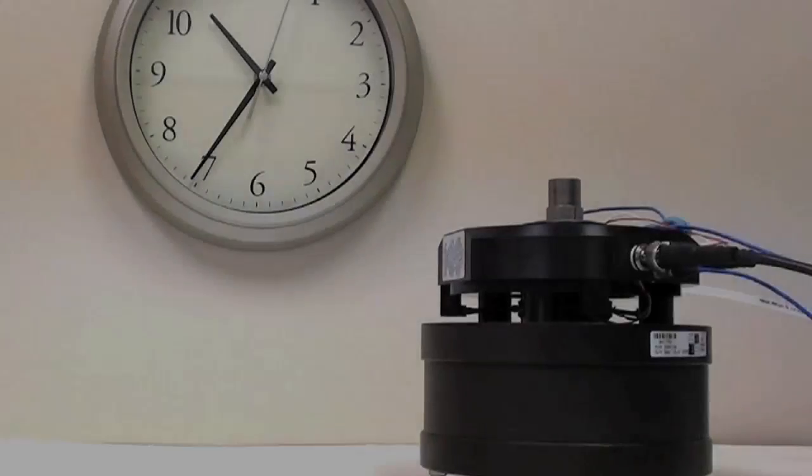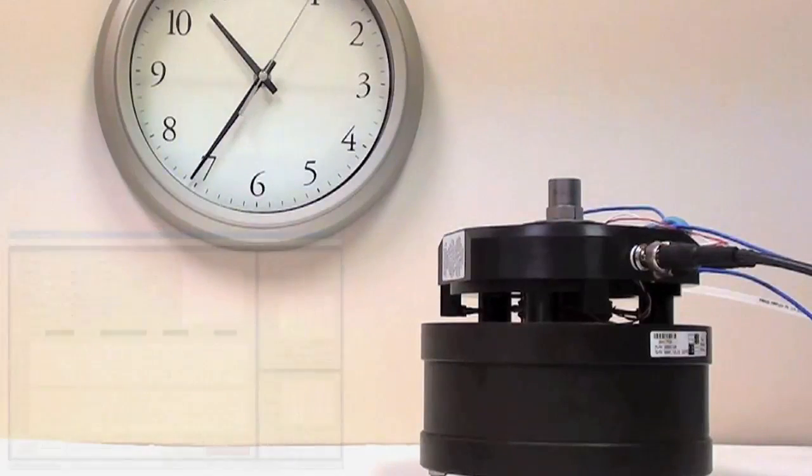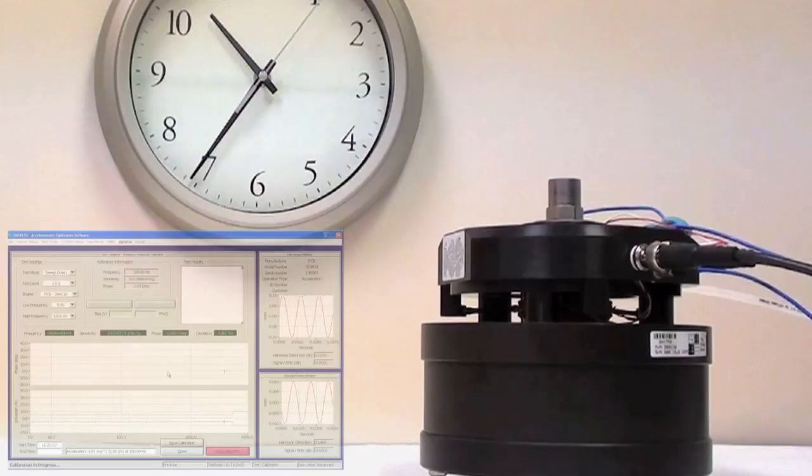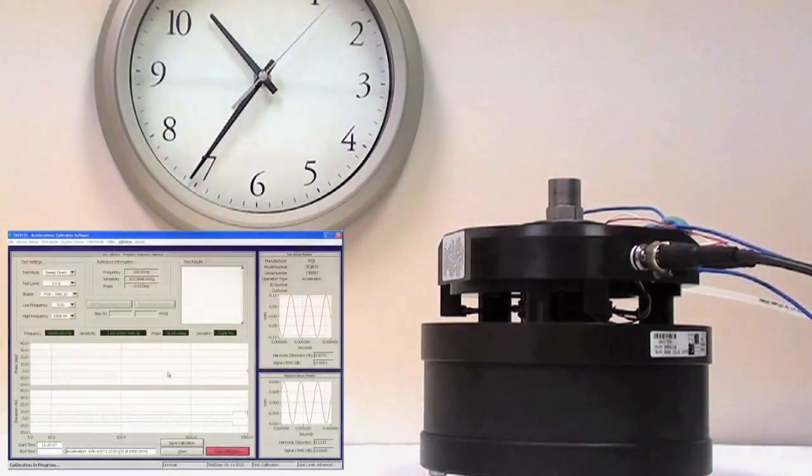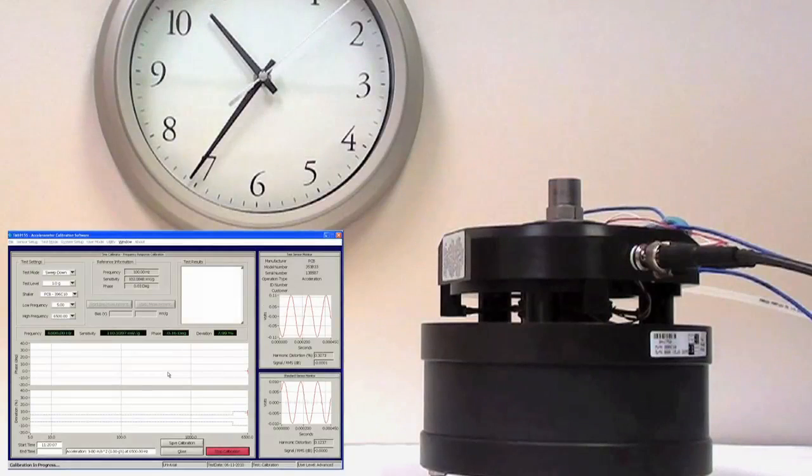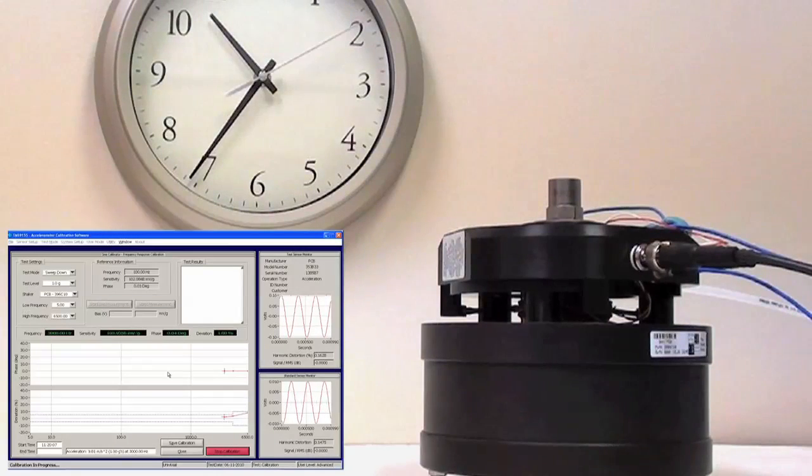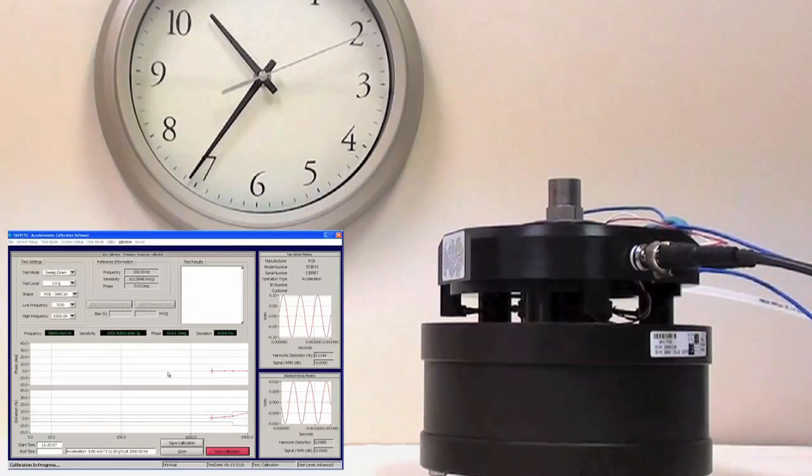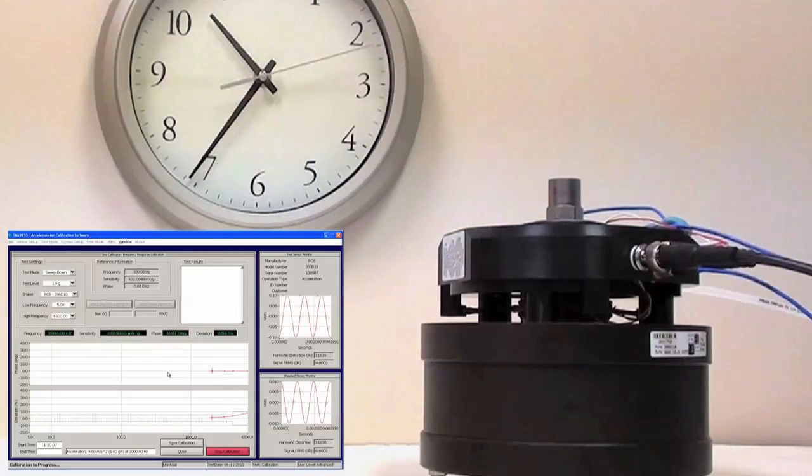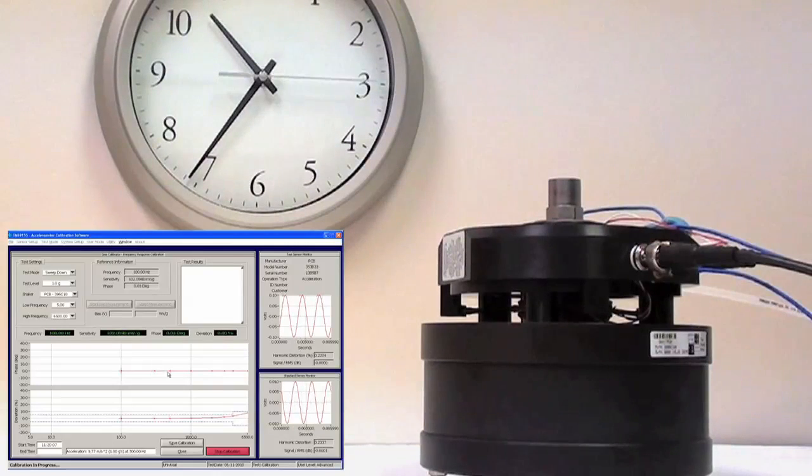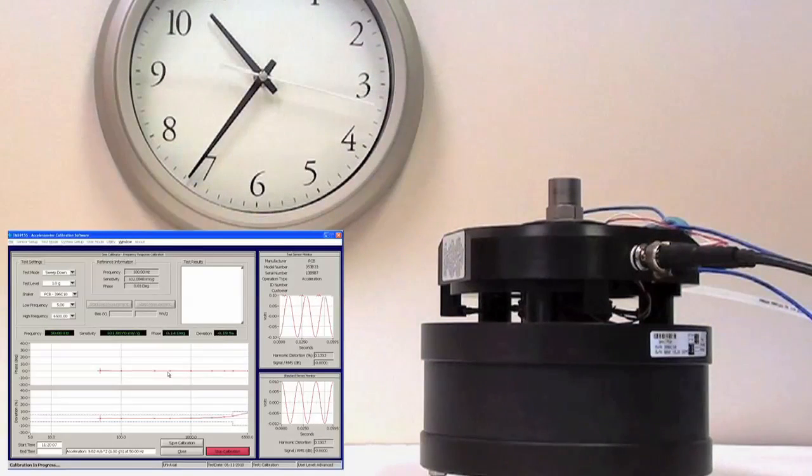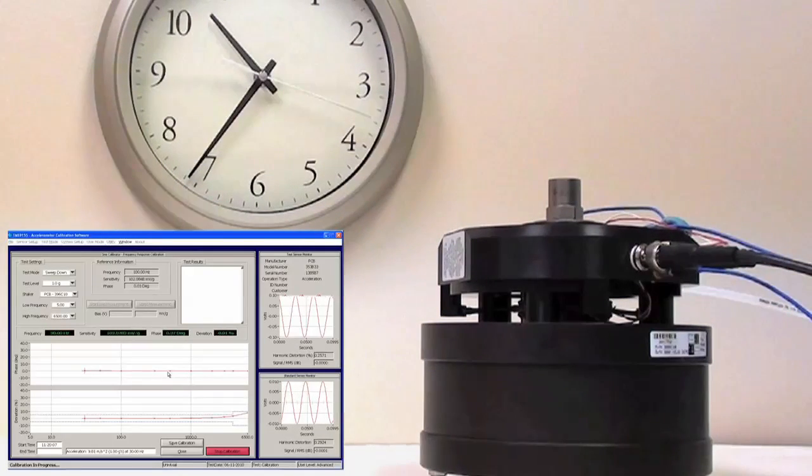A typical step-sine calibration is performed by exciting one individual frequency at a time and using the known sensitivity of the reference standard and the voltage output of the two sensors to determine the sensitivity of the sensor under test.